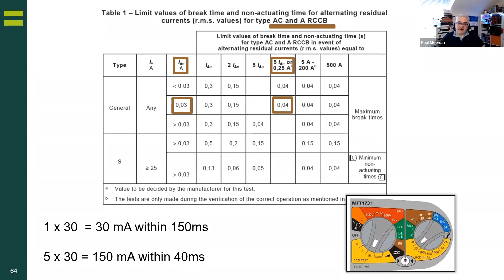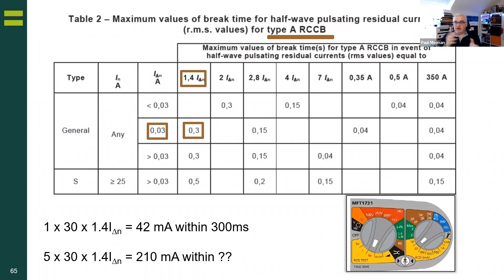So where you've got your I delta N at 30 milliamp, you've got that 300 millisecond trip time, and if you look at the top there, you've got I delta N of 1.4. That's 1.4 times the I delta N. So if you look at the bottom there, 1 times 30 milliamp, sorry, times 1.4 equals 42 milliamps. And that is what our devices are doing to cause the RCD to trip. Now, some of the documents I've read have discussed the 42 milliamp, and it replicates DC by simulating the heating effect that DC causes internally to the RCD, which is why you need more current to produce that same test. But we don't do 5 times anymore.